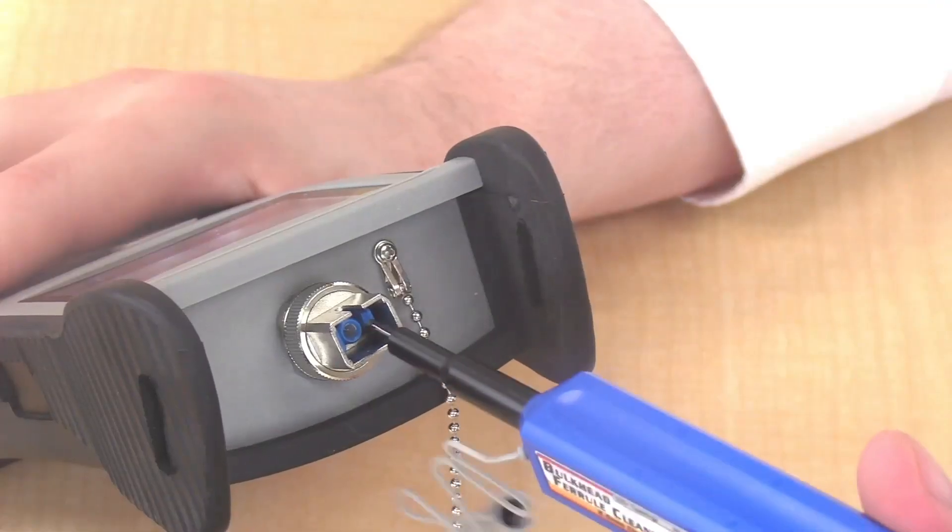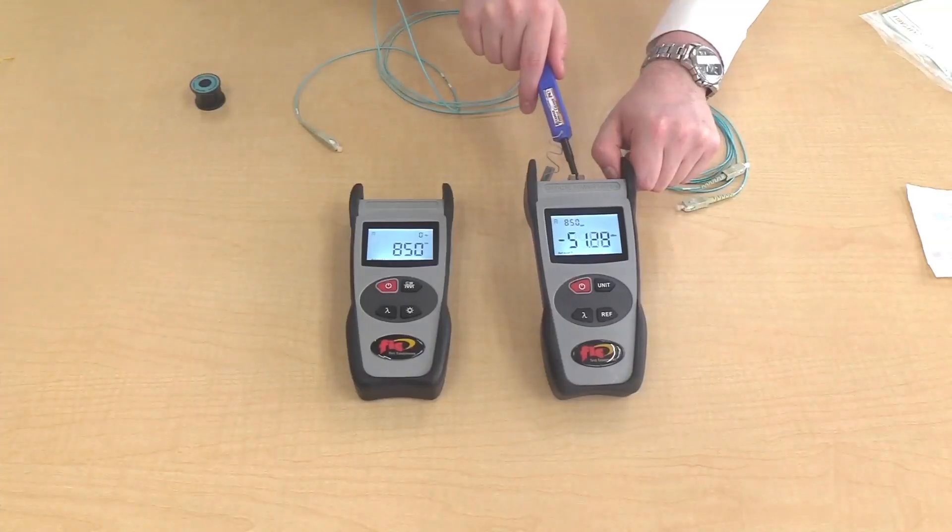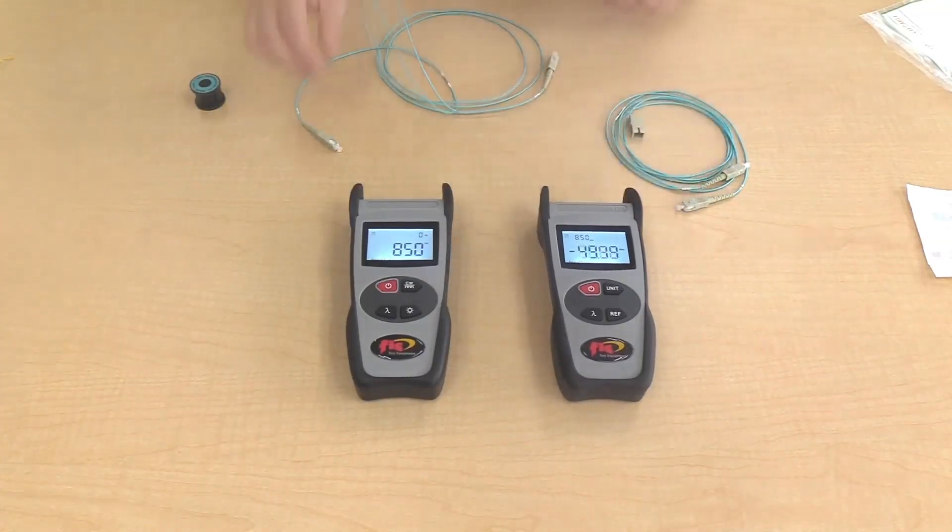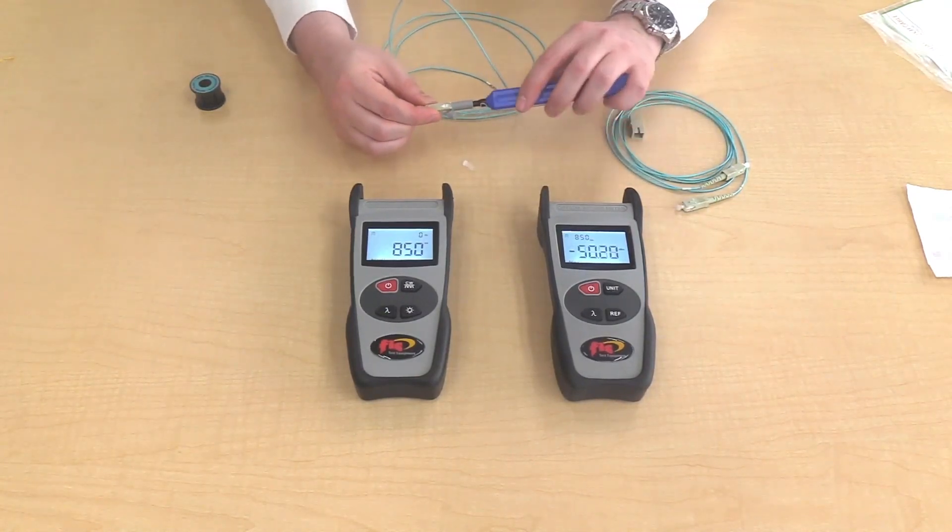First thing you need to do is clean the ports of the light source and power meter. Next, clean the connectors on the reference cord and plug it into the light source and power meter.